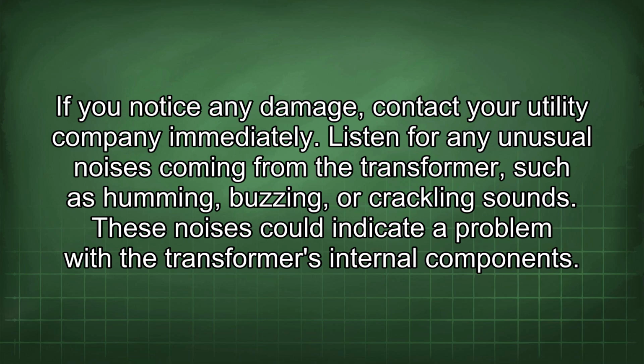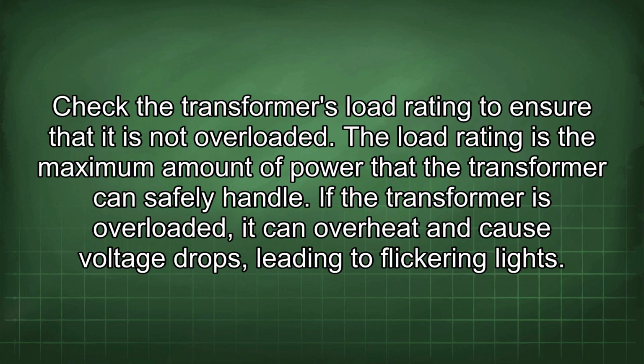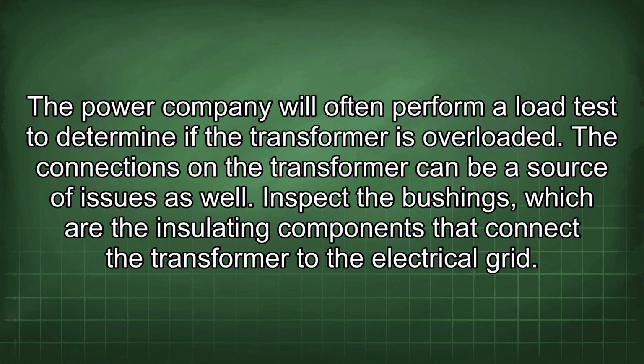Listen for any unusual noises coming from the transformer, such as humming, buzzing, or crackling sounds. These noises could indicate a problem with the transformer's internal components. Check the transformer's load rating to ensure that it is not overloaded. The load rating is the maximum amount of power that the transformer can safely handle. If the transformer is overloaded, it can overheat and cause voltage drops, leading to flickering lights. The power company will often perform a load test to determine if the transformer is overloaded.